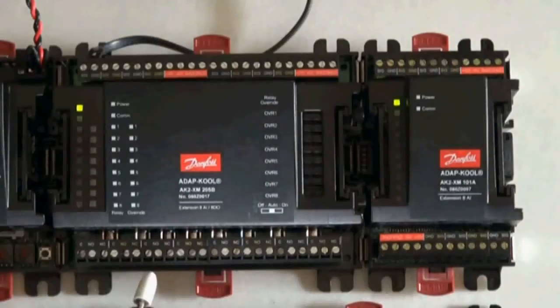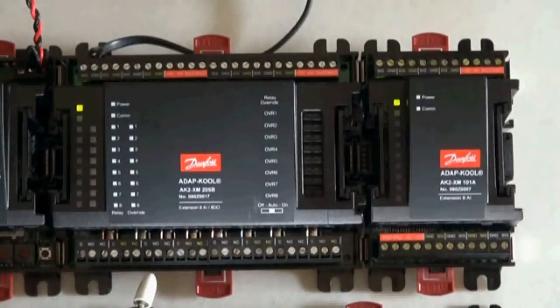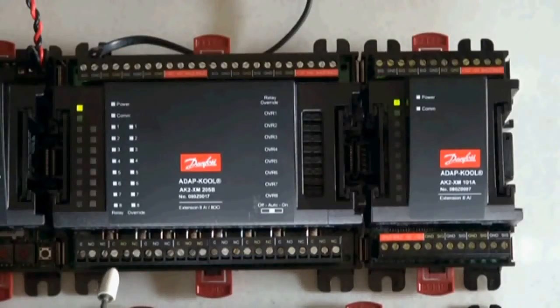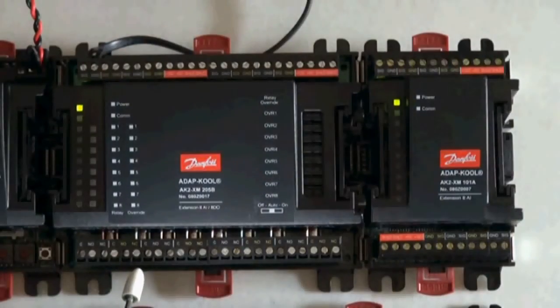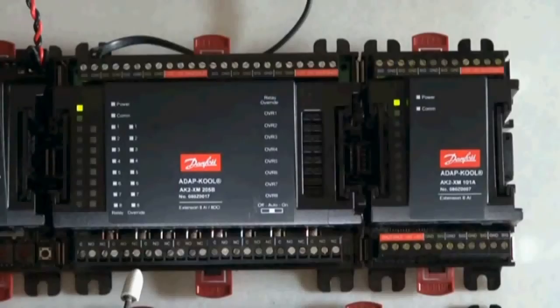Here you see the terminal strip for connecting the loads to the combo board. Each load gives you a common, normally open, and normally closed connection. Relays on the board are fused at 5 amps and 230 volt is the limit.